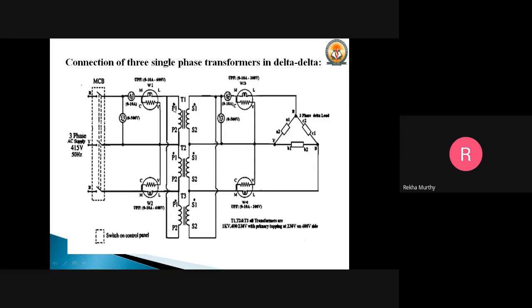Okay, you need not connect it to the 50% tapping, you have to connect it back to the 440 volts which is there on the primary side. That is what you have to take care of. On all three transformers, we need to select 440 volts itself. Okay, on the secondary side, it will remain as it is. You have selected 230, right? So 230 only you have to keep.